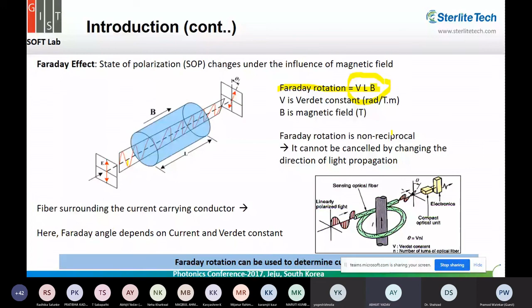Why is it so useful? You have seen the current transformers that we use are very big, with big towers. There is oil there, it can explode, oil leakage, a lot of problems. But these things can go into the past. We can make very tiny transformers by using optical fiber sensors. That is the advantage in that project. We want to replace these big towers of current transformers with tiny fiber optic current transformers.